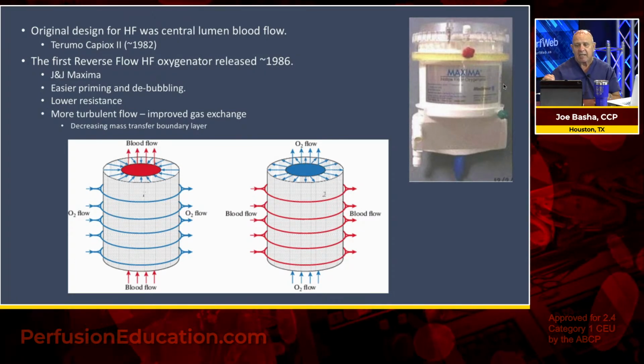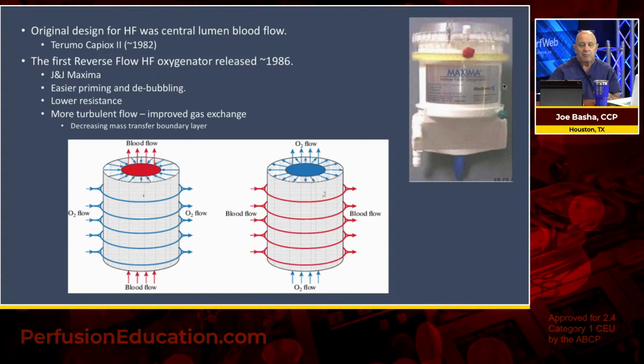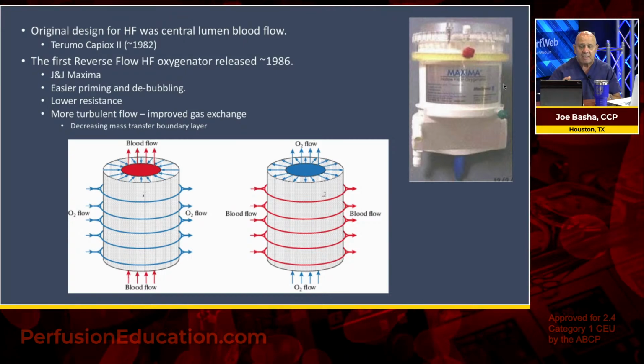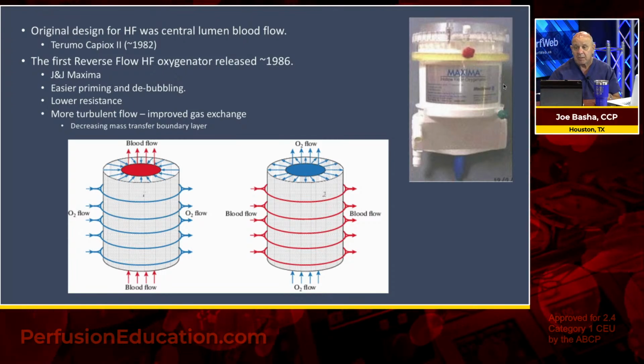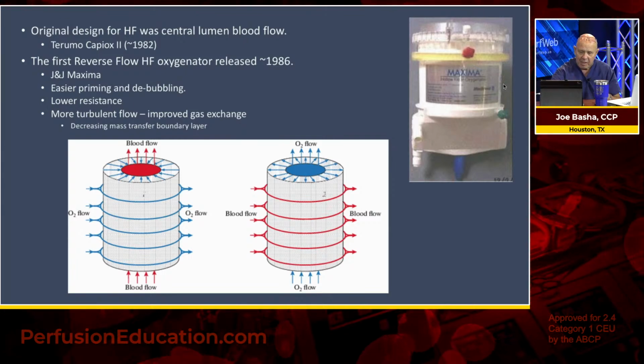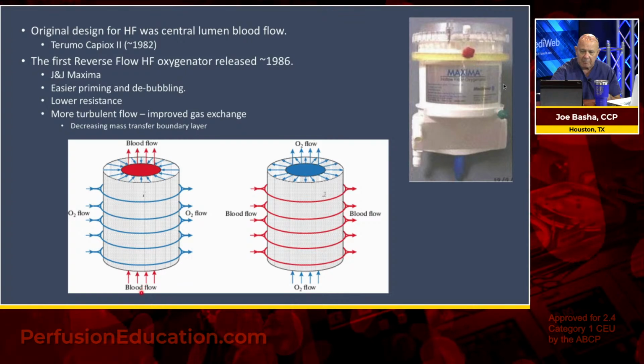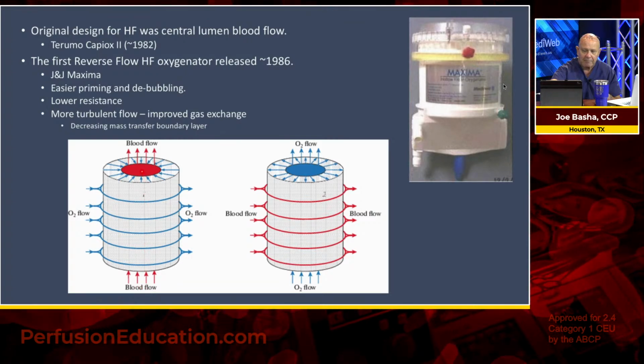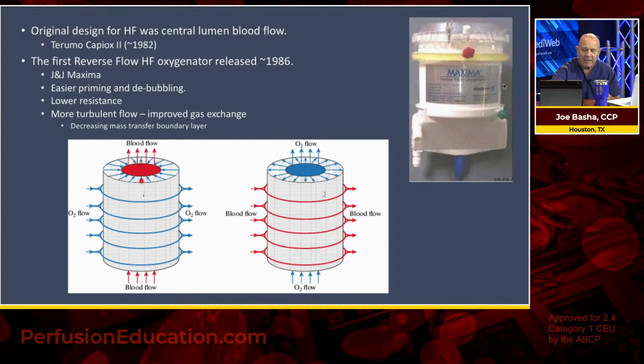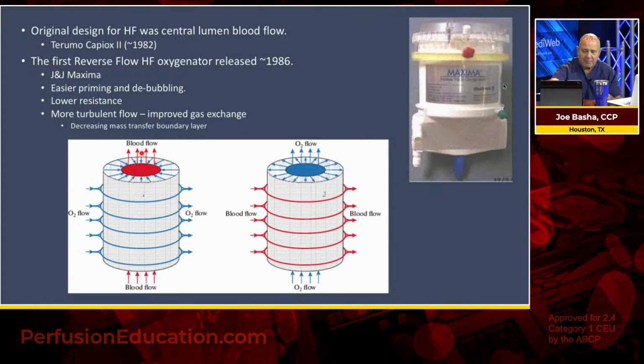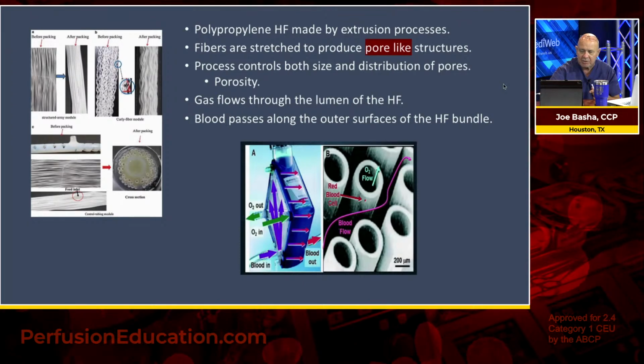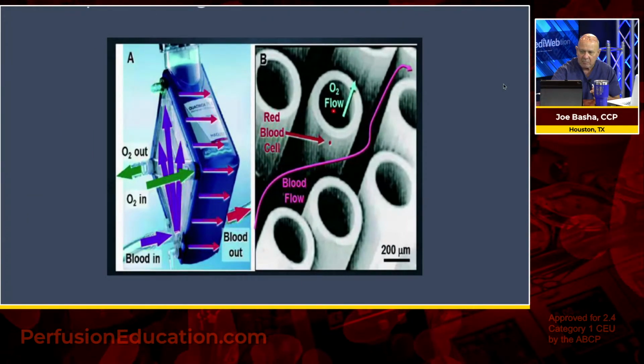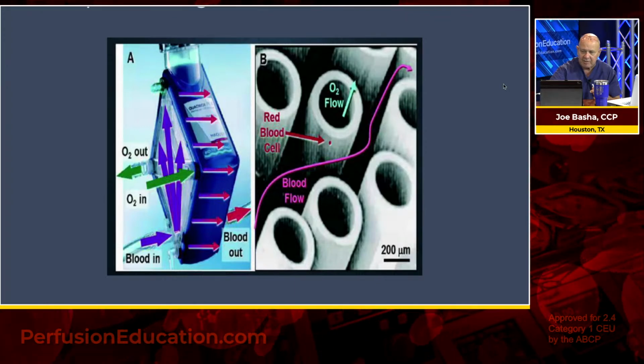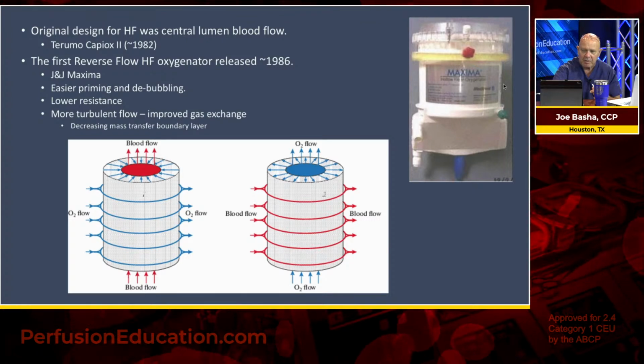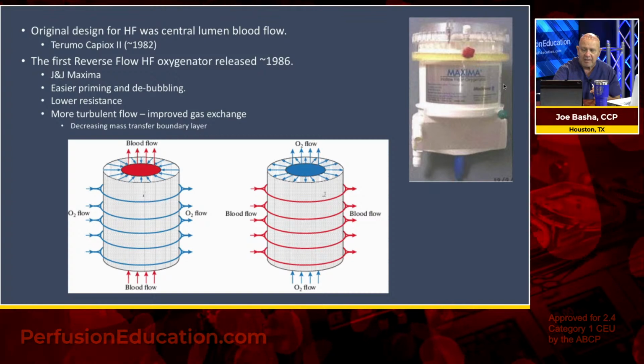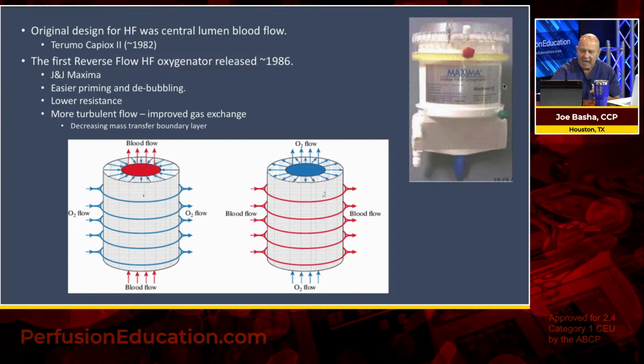But interestingly, circa 1982, the original design for microporous hollow fiber oxygenators was central lumen blood flow, and it was the Terumo Capiox. If you look here on the left, you see the blood coming in, going central lumen, and then the blood flow coming out. So the blood was going through the inner aspect of those fibers, just like you see here where it says O2 flow. Right here, this is where the blood actually was. And that's what you see represented here, with the oxygen or gas flow flowing on the outside of the fibers.